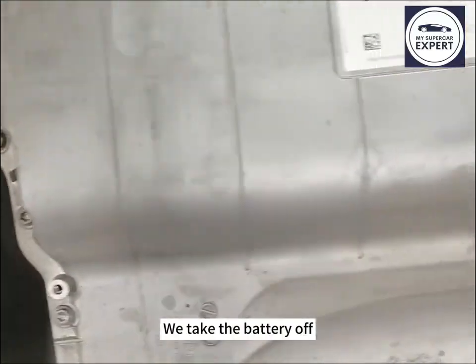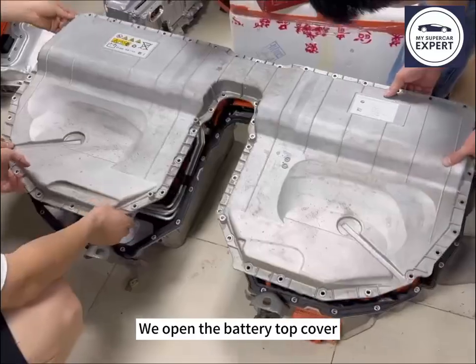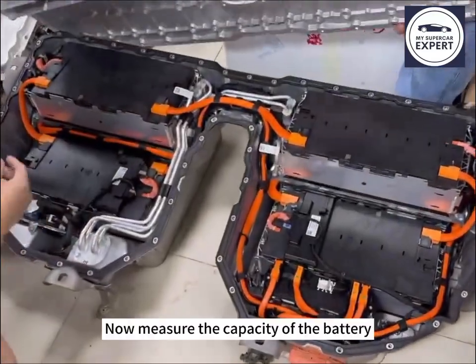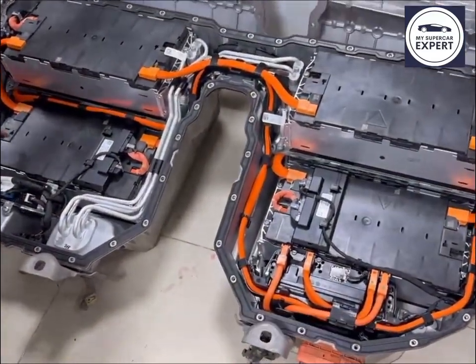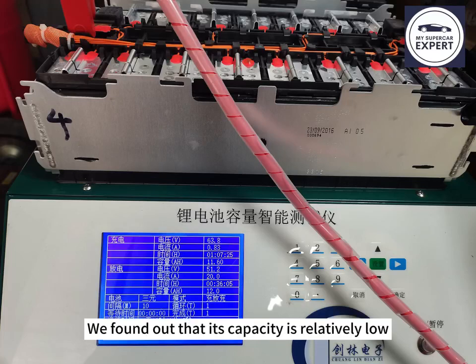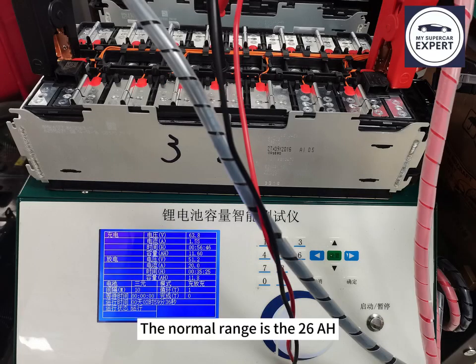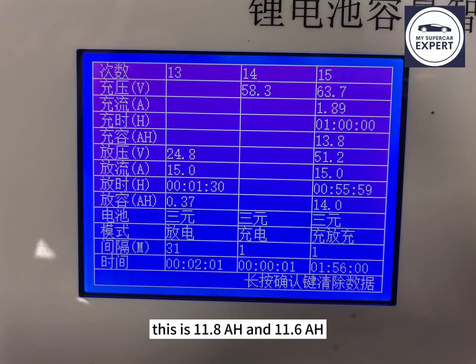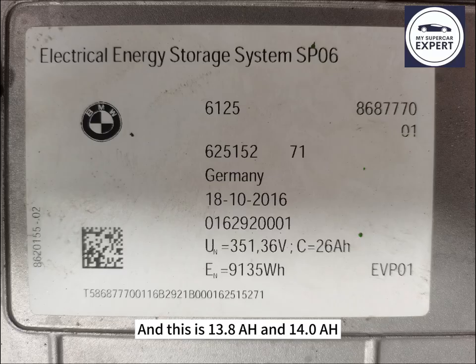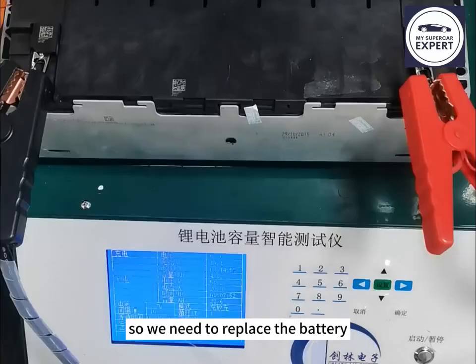We take the battery off. We open the battery top cover. Now measure the capacity of the battery. We found out that its capacity is relatively low. The normal range is 26 ampere hour. There is 11.8 and 11.6, and this one is 13.8 and 14. All those values are too low, so we need to replace the battery.